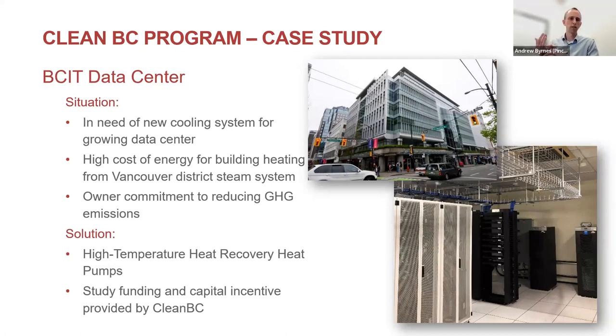That can apply whether it's chiller replacements, boiler upgrades, or adding cooling where it didn't exist before or there wasn't enough capacity. That can be a sweet spot when you have a few needs you can tick off with one program. Our solution here was to use high temperature heat pumps to provide chilled water for the data center cooling systems and supply the heat into the building's hydronic loop. Study funding as well as a capital incentive was provided by CleanBC.